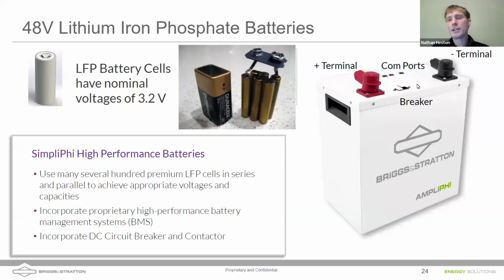There's also an integrated breaker, so we have the ability to turn this off. Each of our batteries has a 100 amp breaker on it, so the battery can output a maximum on the order of 5 kilowatts before tripping this breaker, around 50 volts times 100 amps before we trip that breaker.